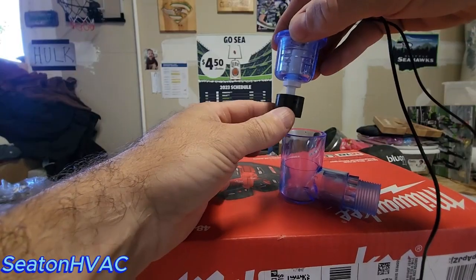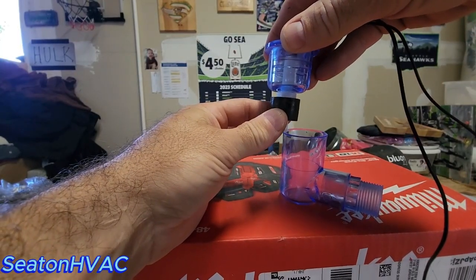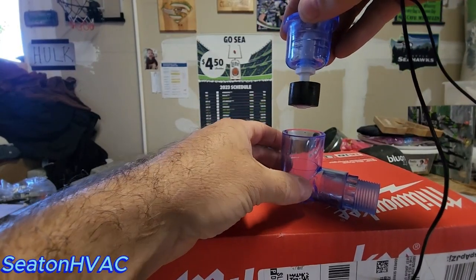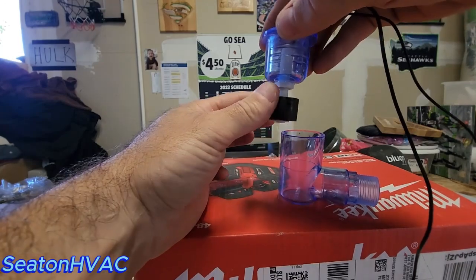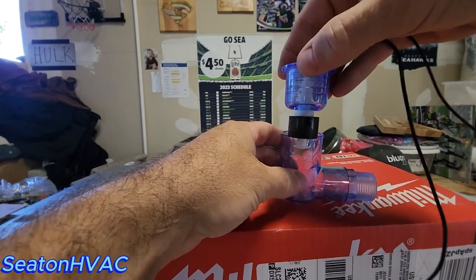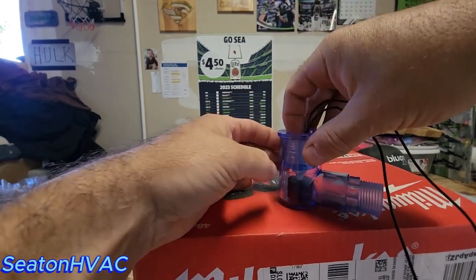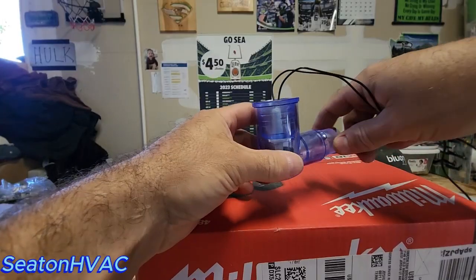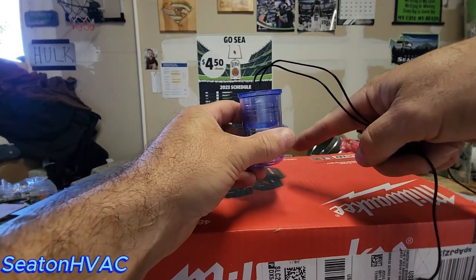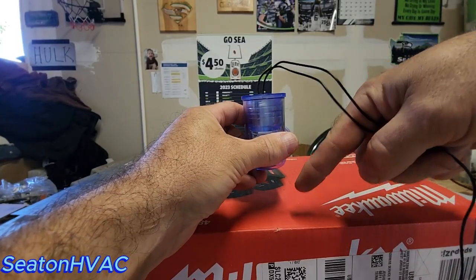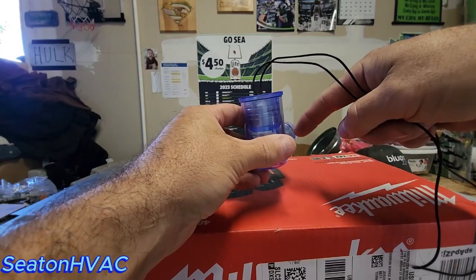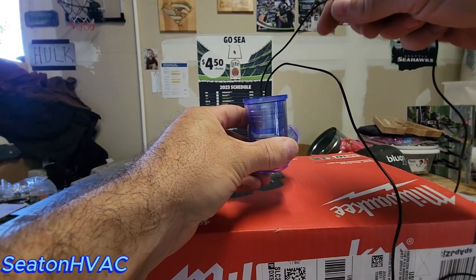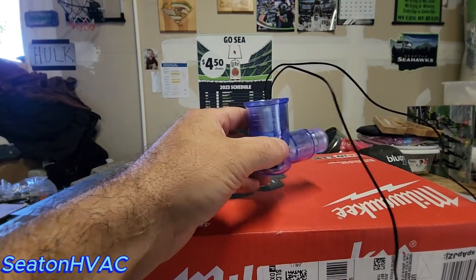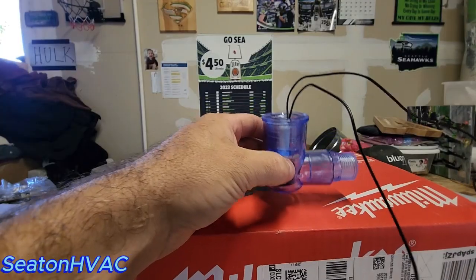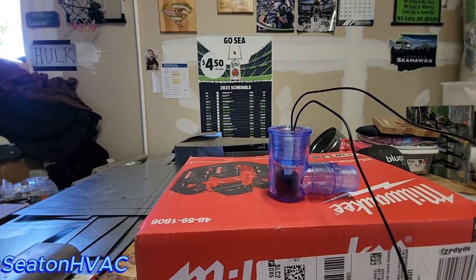If they're a mechanical float like this, that goes up, that opens up your switch. That's down, you're good to go. Your 24 volts will flow through. If it's not with this down, you got a bad switch. That's simple. Easy. What pushes this up? Let's say you put this on the secondary part of your coil, it's a little bit higher than the other one. Your primary drain clogs up, so the water's going to flow through here, push your float up. It's going to save your customer's structure. Very simple. I'm not going to get any more in depth with that. Hope you guys enjoyed the video.